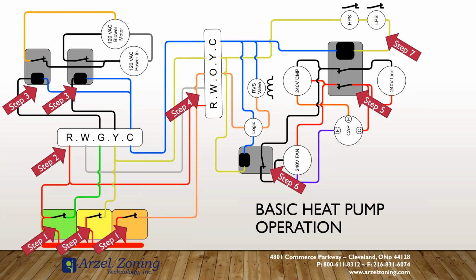So from the Arzel panel, the thermostats are always energized and cooling on the reversing valve, but we'll control that reversing valve operation based on your brand of equipment through the panel itself. In this case, we're just going to say it's energized and cooling. So as we start testing our voltages, we can start to see what's happening. If our motors aren't starting and stopping, it's probably an issue with the high pressure or low pressure switch. Might be a problem with the capacitor. Those are things to look at, but it all comes down to verifying our voltage, verifying our resistance, checking to make sure that the control source is doing what it needs to do. And then if our reversing valve is energized or if it's de-energized, determines whether or not we have a call for heating or whether or not we have a call for cooling.